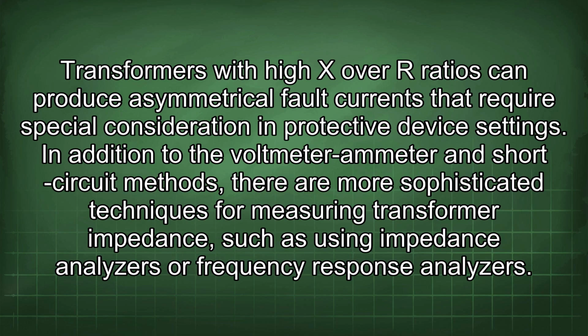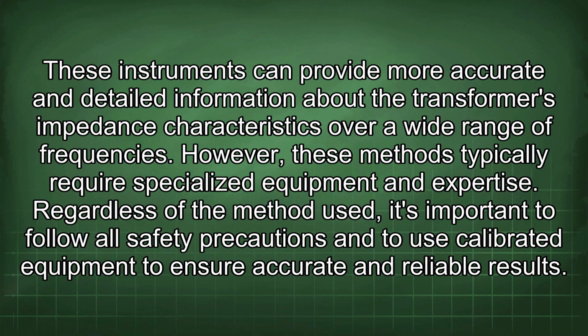In addition to the voltmeter, ammeter, and short-circuit methods, there are more sophisticated techniques for measuring transformer impedance, such as using impedance analyzers or frequency response analyzers. These instruments can provide more accurate and detailed information about the transformer's impedance characteristics over a wide range of frequencies.